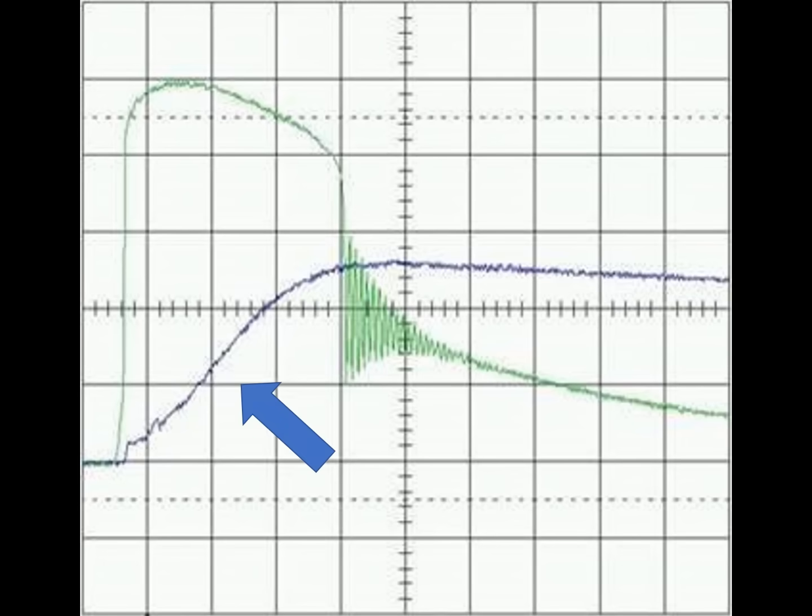The blue waveform is the let-through for a series filter. This shows a much lower rate of voltage change as well as a significantly reduced peak voltage.